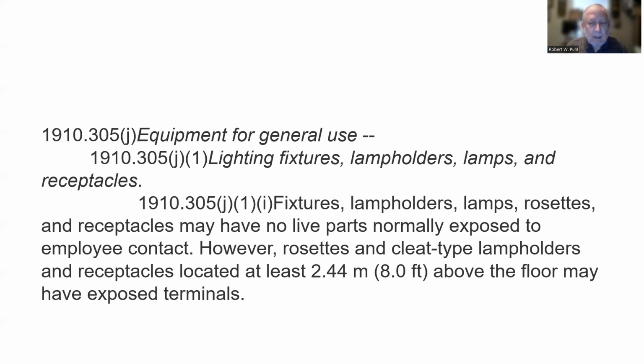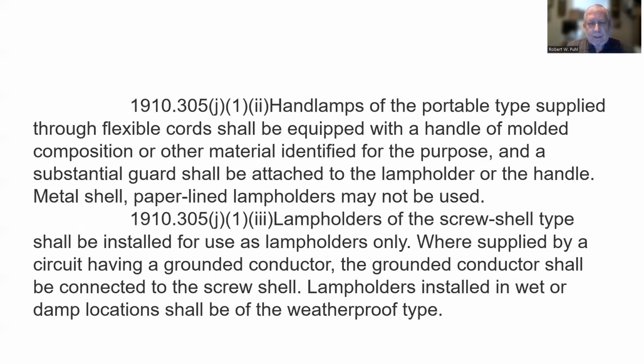So 8 feet, okay. Now, I might take a little bit of exception to something that's electrical and open, because at 8 feet above it, you could still hit it with something you're carrying. So you have to be careful about that. Hand lamps of the portable type supplied through flexible cords shall be equipped with a handle of molded composition or other material defined for the purpose, and a substantial guard shall be attached to the lamp holder or the handle. Metal shell paper-lined lamp holders may not be used. I don't even think these are around anymore, but they might be.